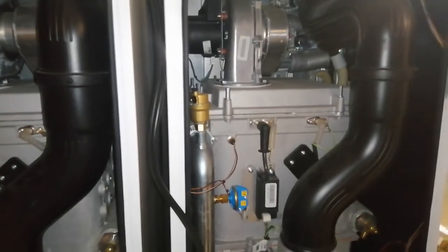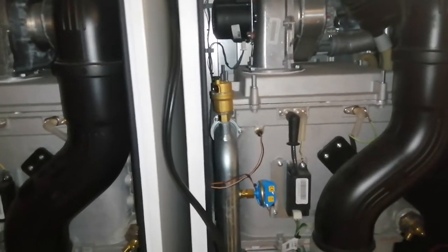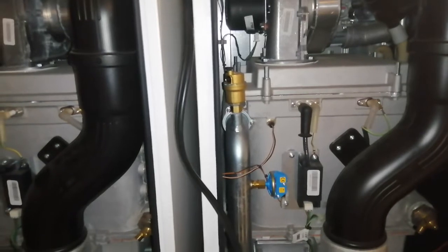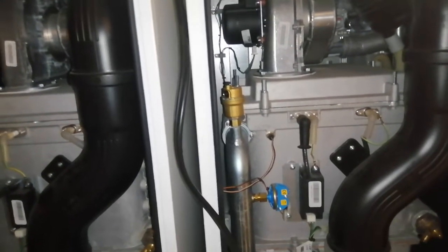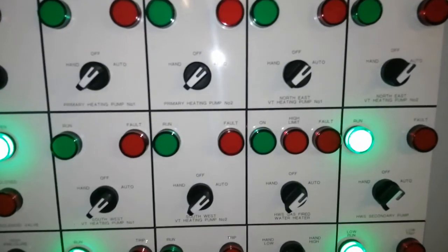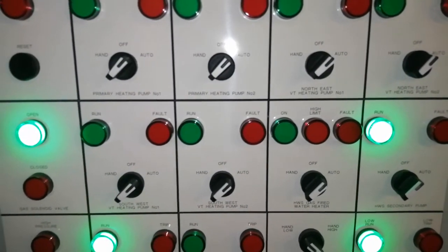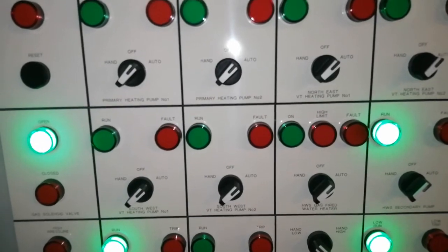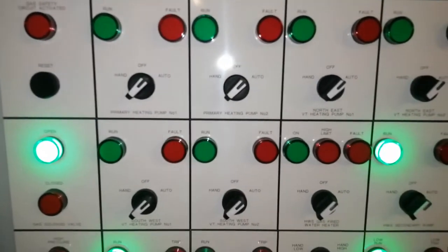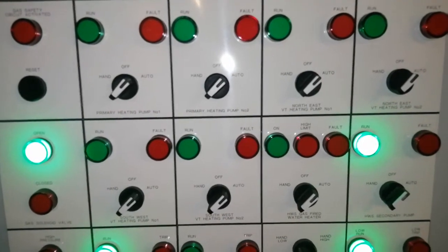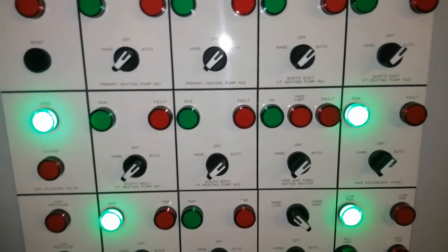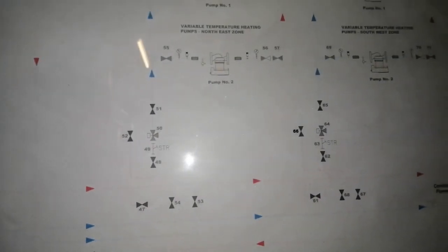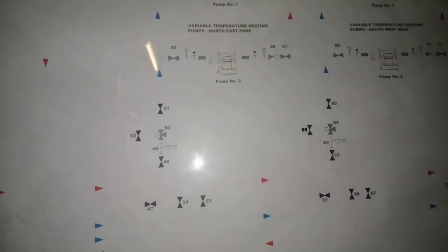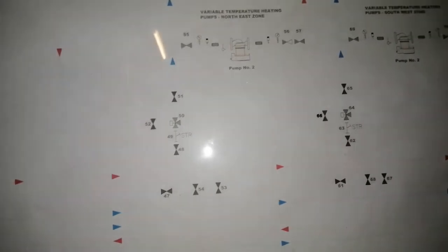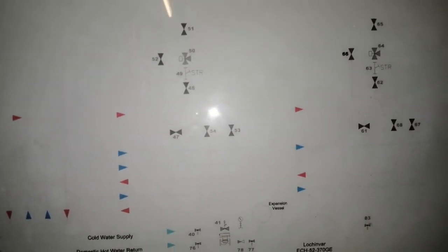So i.e. the hot water temperature is not dropping whilst you're switching off boilers and so on, or temperatures aren't going too high if you're bypassing any of the controls. Have a look at your BMS. Take a picture if you have to of what the settings are before you start your work, if there's any reset buttons and so on, and if there's any alarms on the BMS as well, take a note of them. Also have a look at the schematics, so you see what's serving hot water and so on, what's serving heating, and the general setup of the plant room.